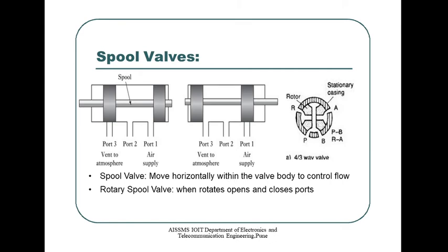The spool valve is the simplest type of directional control valve. It consists of a spool, which is a cylindrical member that has a large diameter spool land, which slides in a very close fitting bore of the valve body. The rotary spool valve consists of a rotating spool which aligns with the ports in the stationary valve body so that the fluid is directed to the required ports. When it is rotated, that allows opening and closing of the ports.